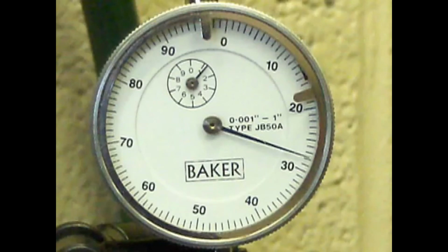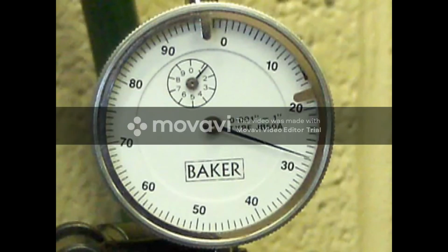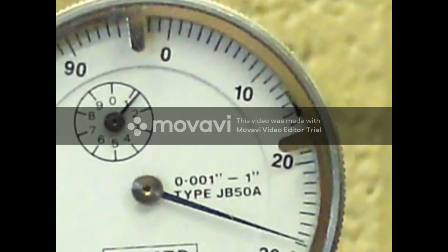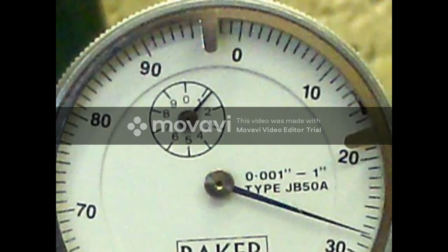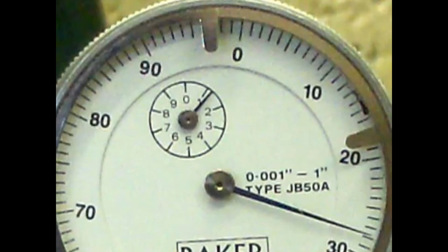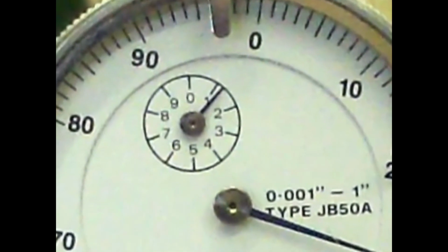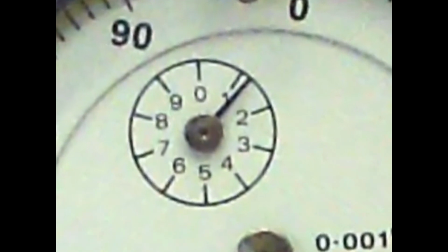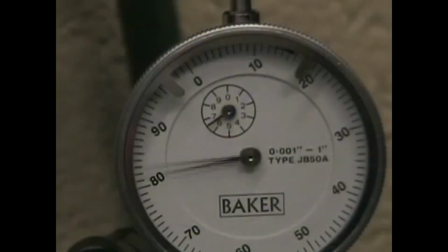There are two scales on the dial indicator. The outer scale is marked in 1/1000th of an inch increments, and each 10th number is marked to make reading easier. The small inner scale is numbered 1 through 9, and each number represents one-tenth of an inch. For each complete revolution of the outer scale, the small inner scale moves one number up or down.